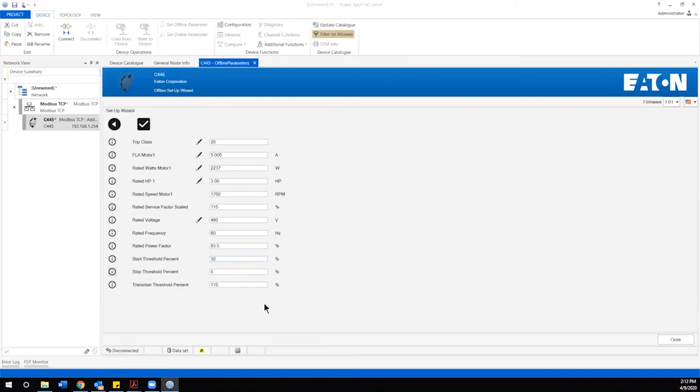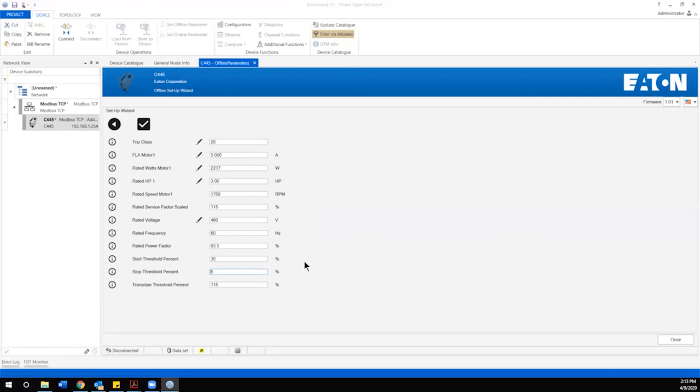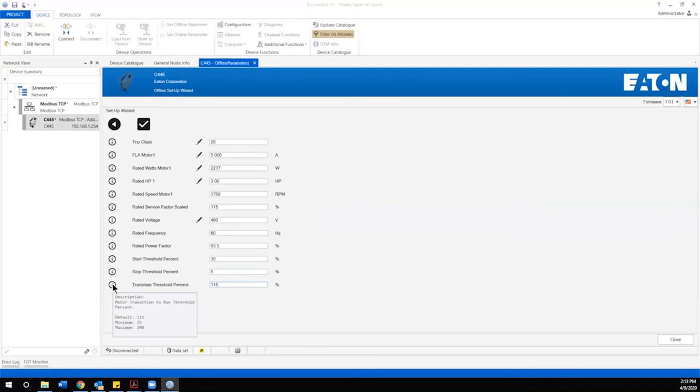The next parameter is the stop threshold and this is the inverse of the previous and this is what the system uses to define that the motor is stopped and our default here is five percent and then for general applications that is well within the requirements. Our last parameter that we would look to change potentially is the transition threshold percentage and again this is the motor transition to run so this is that process from startup to running and 115 percent is default and within a good range for a general application.